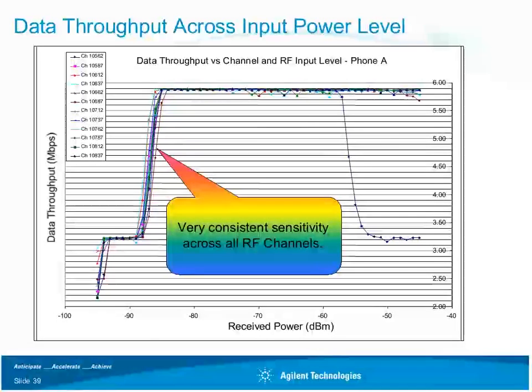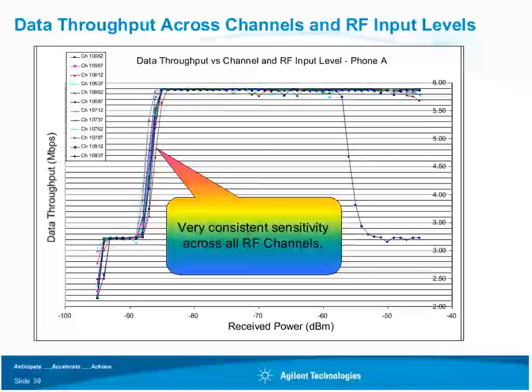Okay, more of the same device. This is the channel that drops off, and you can see here's all of the RF channels from the high band to the low band. You can see this sensitivity point is pretty consistent across all those RF channels, which says that device is pretty well calibrated so that all your RF performance across the frequency band works very well, except for this one band edge that we've discovered.